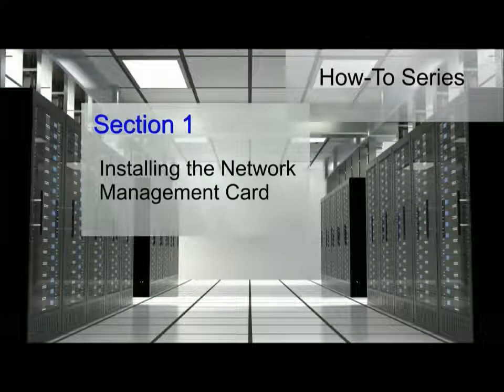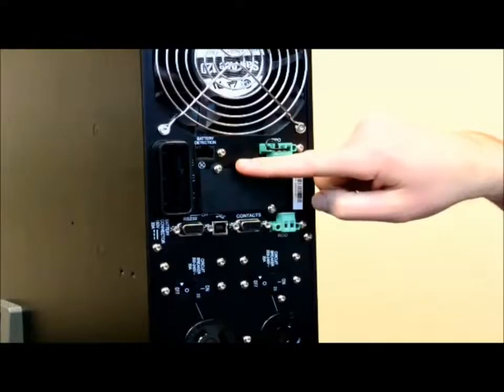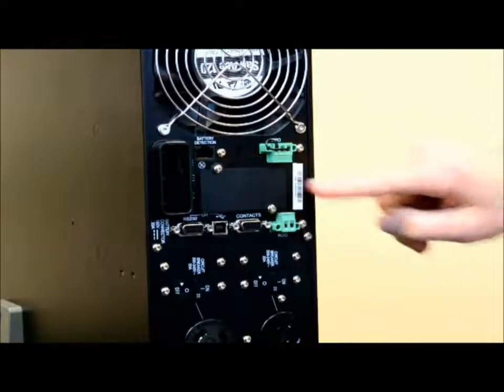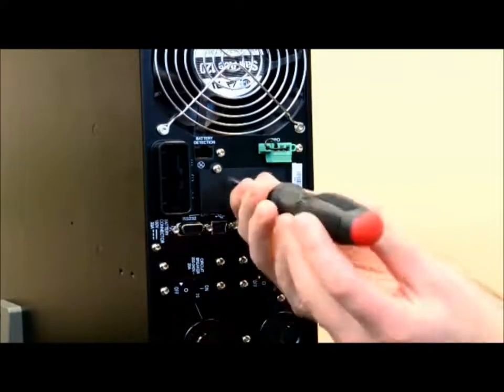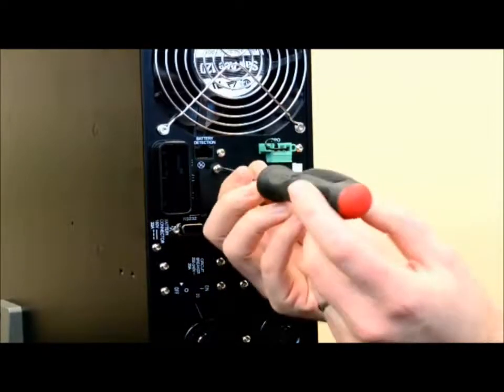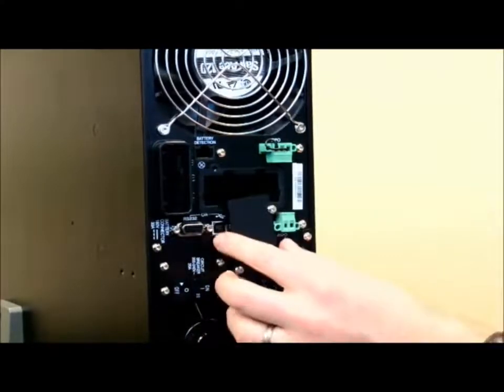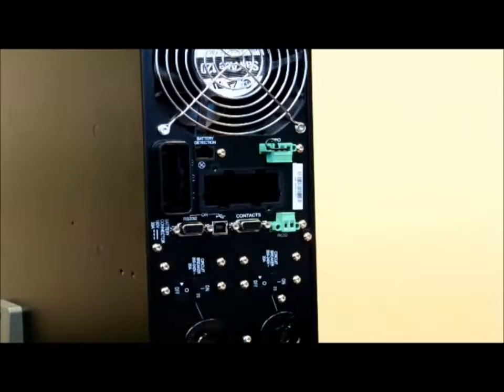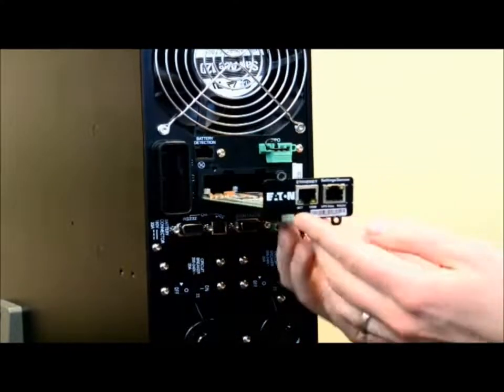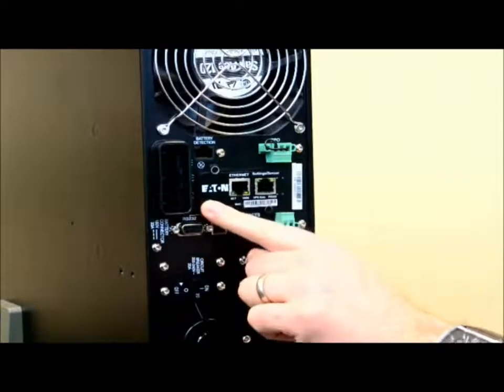The network management card is hot swappable, which means that the card can be installed into the UPS without shutting it down. Locate the blanking cover on the back of the UPS. Using a Phillips screwdriver, remove the retaining screws from the blanking cover. Remove the blanking cover from the UPS. Line the network management card up with the open slot and insert.